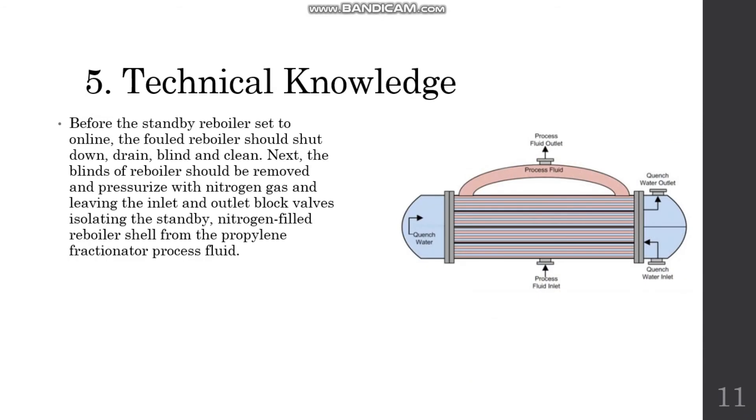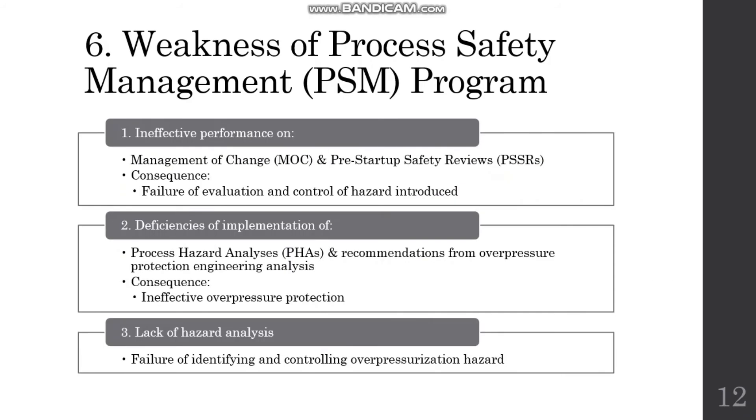Regarding technical best practice: before setting a standby reboiler online, the fouled reboiler should first be shut down, drained, blinded, and cleaned. Then the blind should be removed, the reboiler pressurized with nitrogen gas, and the inlet and outlet block valves used to isolate the standby reboiler from the distillation column.